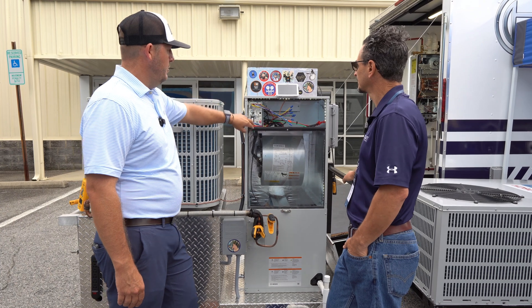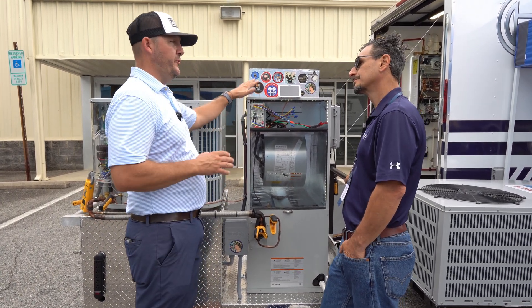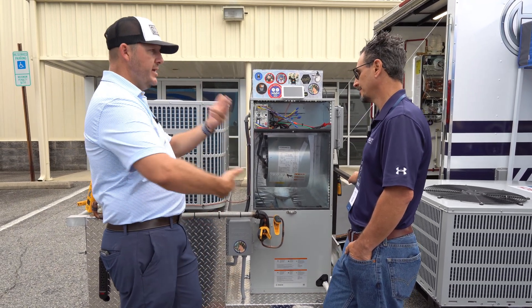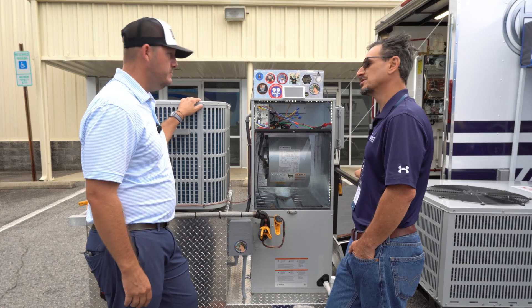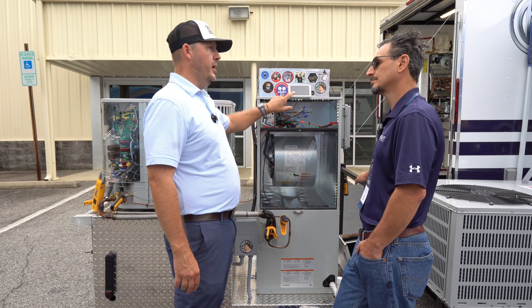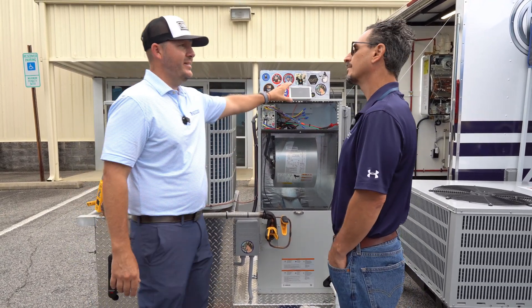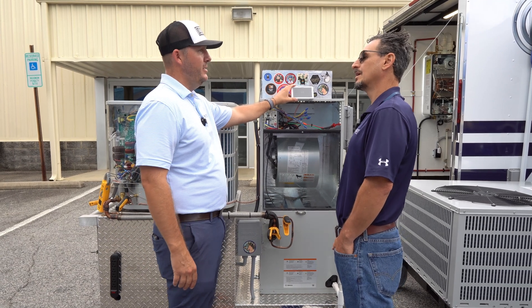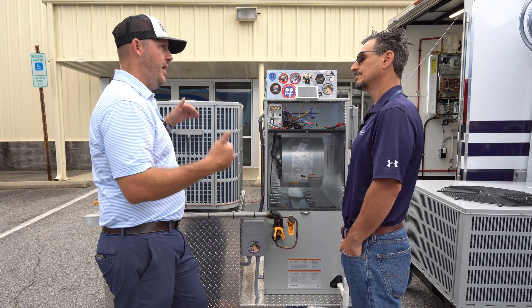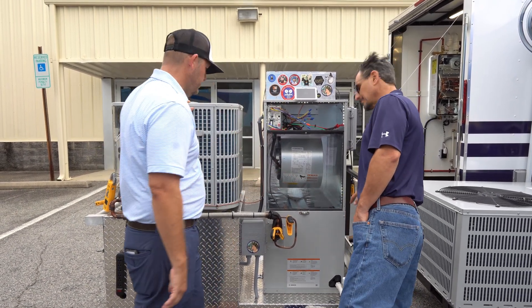Air handler is an air handler — I don't know if these will ever get fancier, residential-wise. There's a Danfoss TXV in here. It does have dehumidification, which all that does is slow the blower down to first speed — great way to extend run time. It's actually measuring the space RH. You can set this to whatever humidity level you want, but the only way to dehumidify is to turn this off, so you have to consider how much you want to overcool. You can extend run time on here.